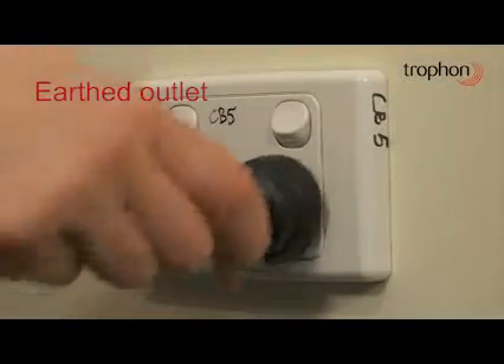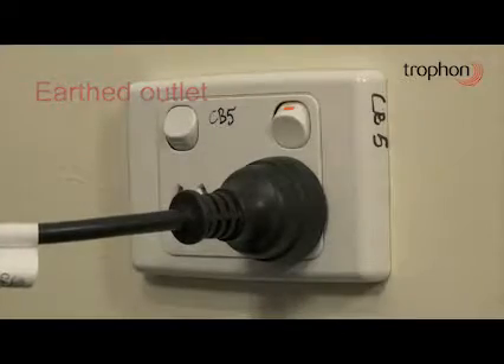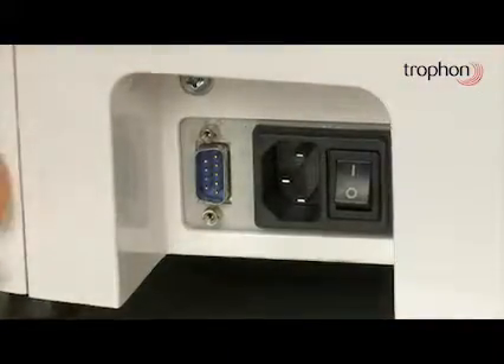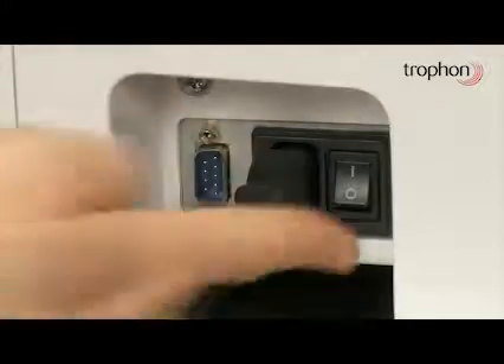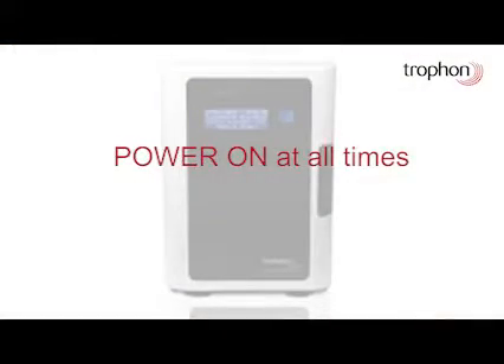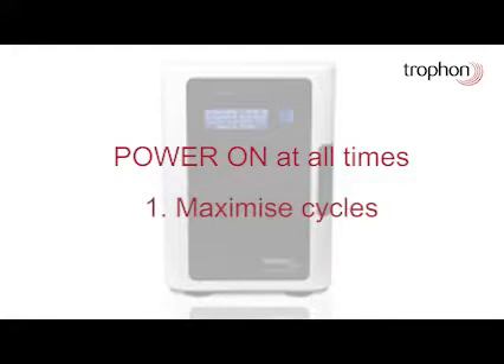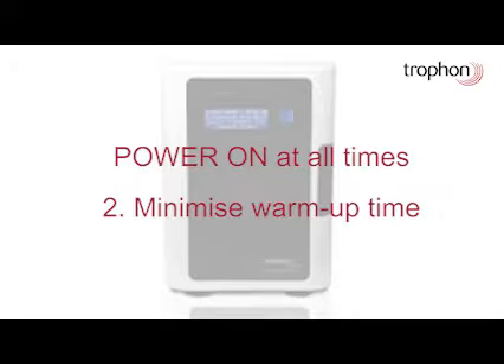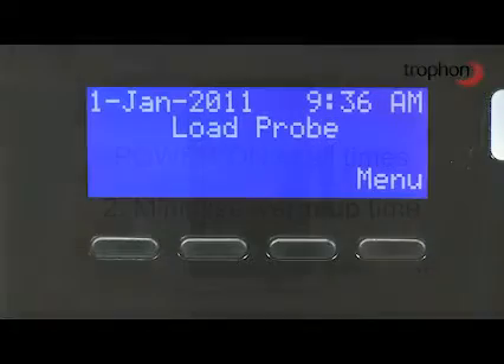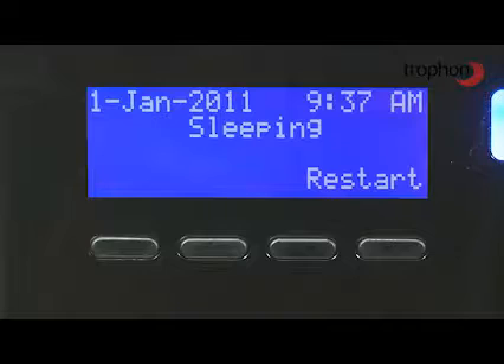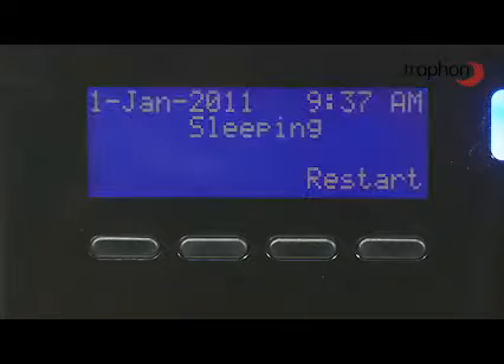Your Trophon EPR must be connected to an earthed outlet using the power cable supplied. Turn on your device using the power switch. Your device should remain powered on at all times for 2 reasons. 1. To maximize the number of cycles obtained from each disinfectant cartridge. 2. To minimize Trophon EPR warm-up time. Your Trophon EPR will automatically enter sleep mode after a period of inactivity to save power.